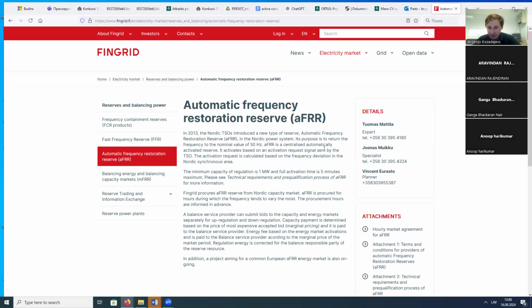aFRR is a centralized, automatically activated reserve. This is very important - what is the difference? It's centralized, automatically activated reserve, meaning it activates based on the activation request signal sent by the TSO. The activation request is calculated based on the frequency deviation in the Nordic synchronous area, and not only the frequency deviation, but the deviation speed as well. The minimum capacity of regulation is 1 megawatt and full activation time is 5 minutes maximum.